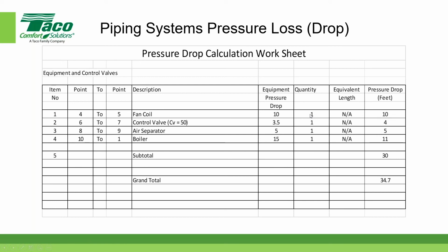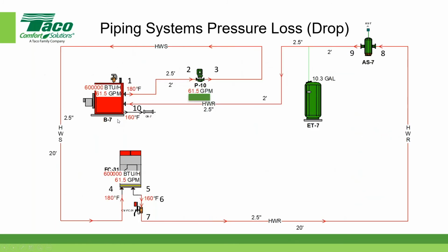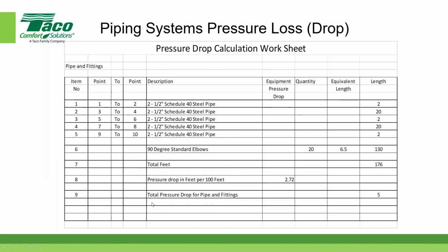Now, obviously, if I had 3 fan coils in series, then I'd simply change this quantity from 1 to 3, and my pressure drop would be 30 feet if it was 10 feet for each one. Now we have the control valve. In this case, my control valve is from point 6 to point 7. Let's go back to our diagram. There's point 6 and there's point 7, and between those 2 points is the control valve.